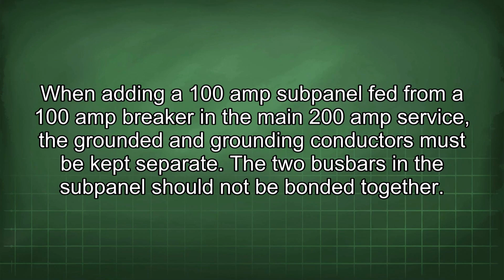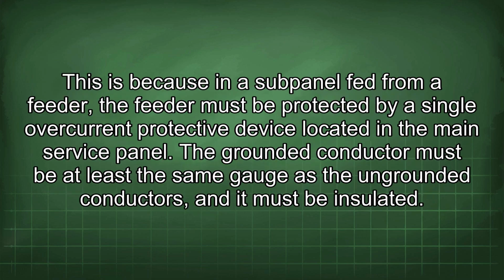When adding a 100 amp subpanel fed from a 100 amp breaker in the main 200 amp service, the grounded and grounding conductors must be kept separate. The two bus bars in the subpanel should not be bonded together. This is because in a subpanel fed from a feeder, the feeder must be protected by a single overcurrent protective device located in the main service panel.